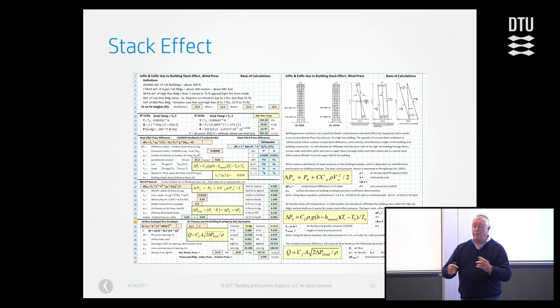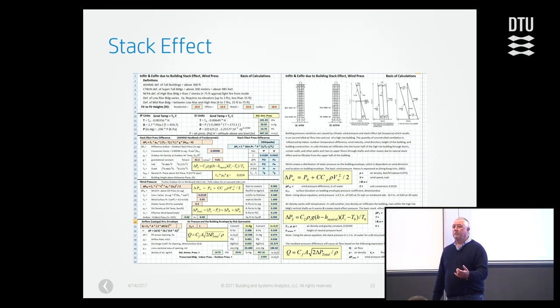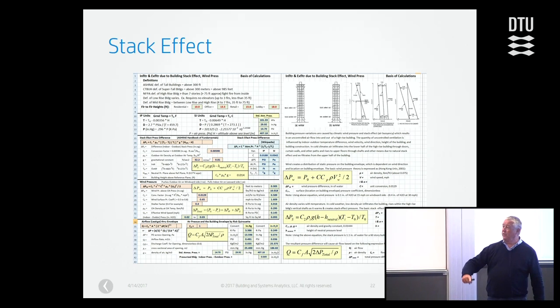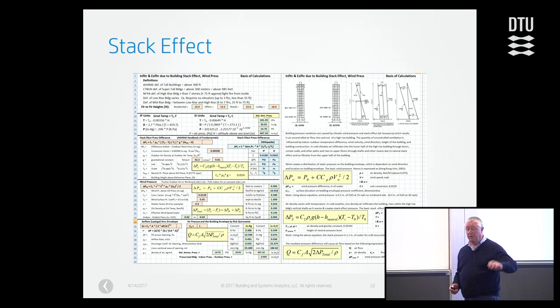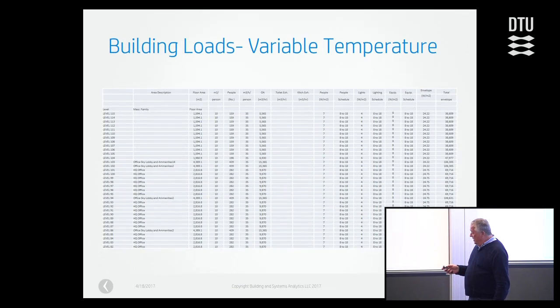When you start opening windows, all bets are off, because that neutral pressure can float up and down the building. So when the fire marshal or the captain comes along and wants to know where the fire's going to be, how the pressure's going to behave, whether the exhaust fan's going to work, whether you're going to get smoke out of the building, and you tell him the neutral pressure is doing this, you're back to your 1,000-meter ladder outside, because he's not going to guarantee you'll get smoke evacuation. I apologize for this.